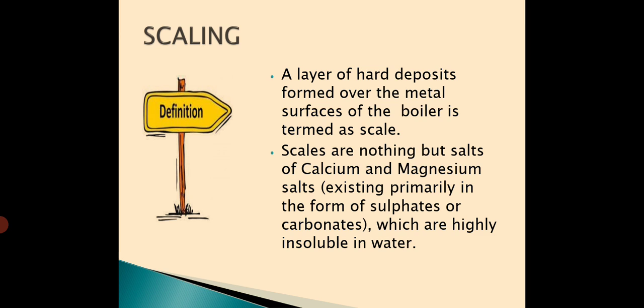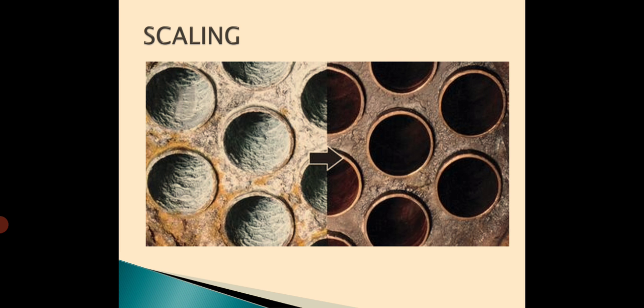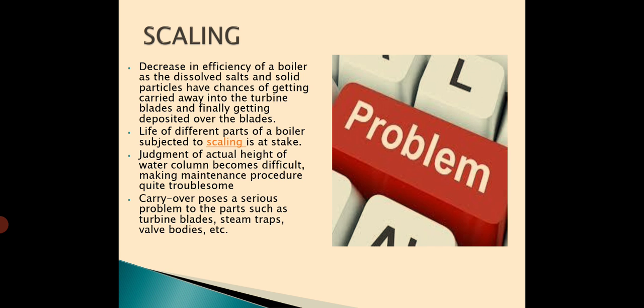What is a scale? A scale is a hard deposit which is formed over the metal surface of a boiler. These scales are nothing but the salts of calcium and magnesium which exist primarily in the form of sulphates or carbonates which are highly insoluble in water. As they are highly insoluble in water, when the water inside the boiler boils or is converted into steam, these salts get precipitated and get adhered to the surface of the boiler forming hard deposits. In this picture you can see the presence of scales inside the boiler surface.